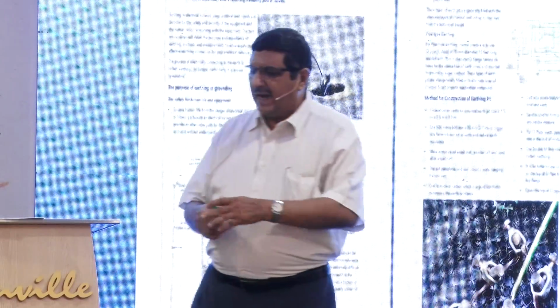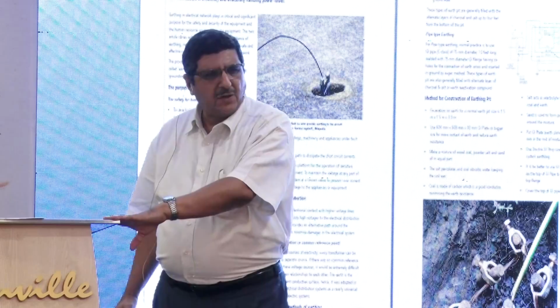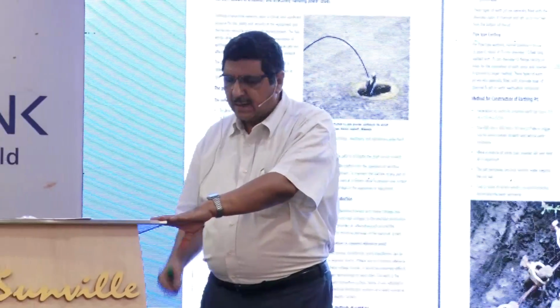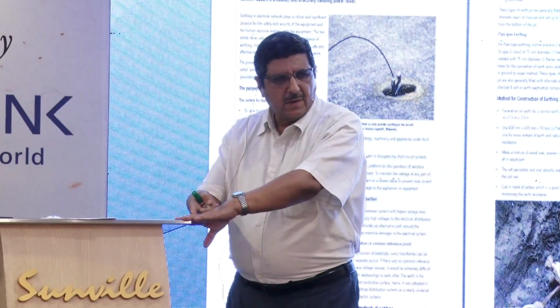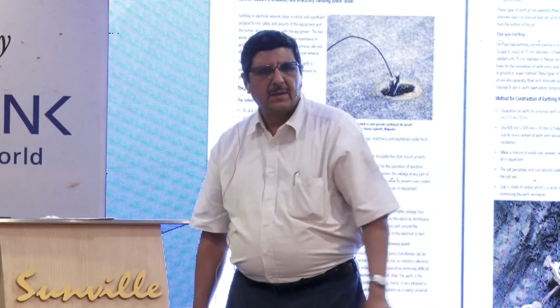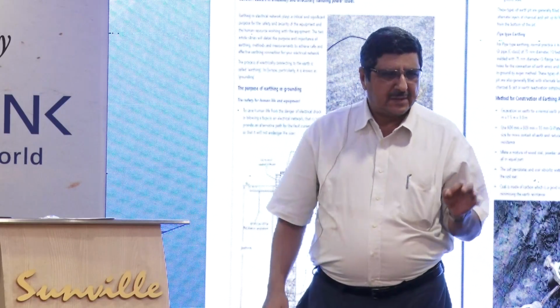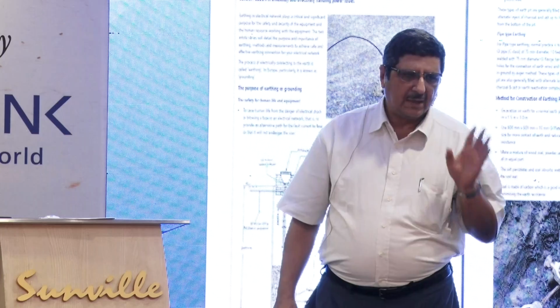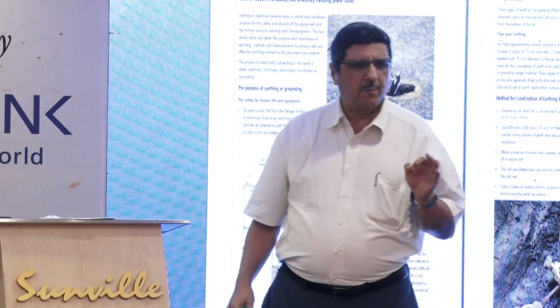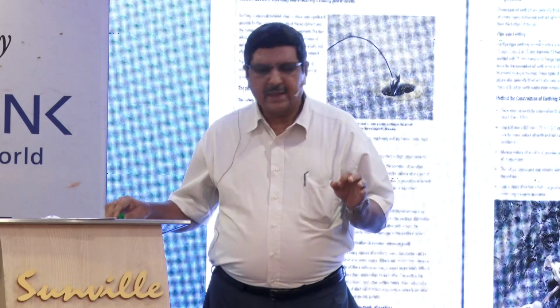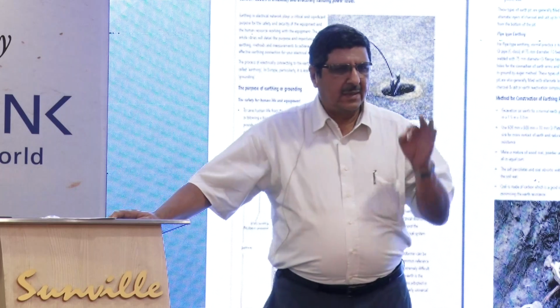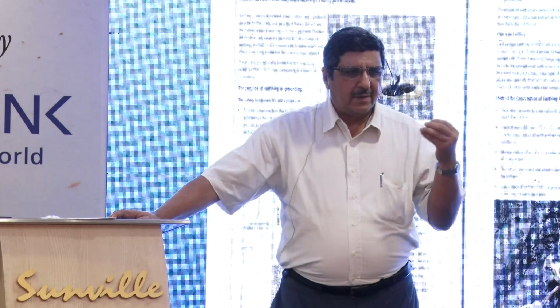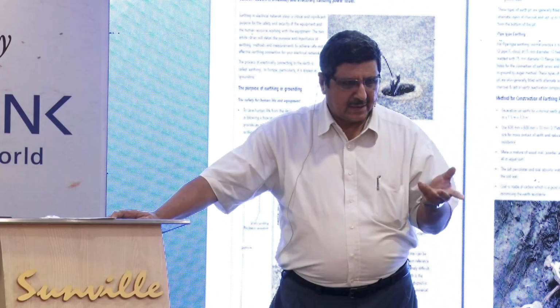So let's say if a child touches a fridge which has no earthing, the current that passes through the body, around 8 to 10 milliamperes, is liable to kill a child. In an adult human body, anything around 22 to 25 milliamps is liable to kill if it exceeds more than 2 to 3 seconds.